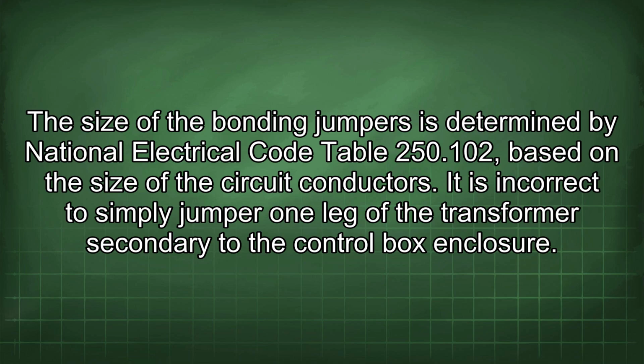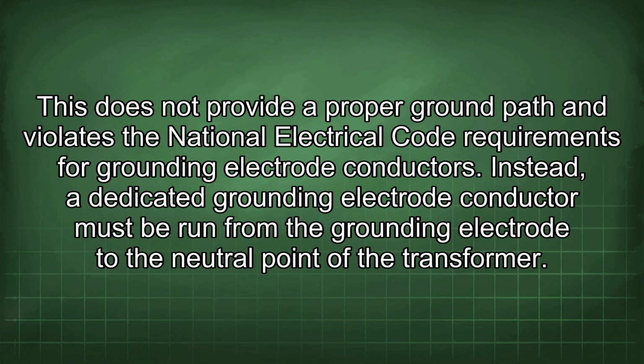It is incorrect to simply jumper one leg of the transformer secondary to the control box enclosure. This does not provide a proper ground path and violates the National Electrical Code requirements for grounding electrode conductors. Instead, a dedicated grounding electrode conductor must be run from the grounding electrode to the neutral point of the transformer.